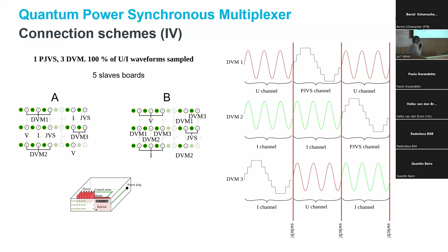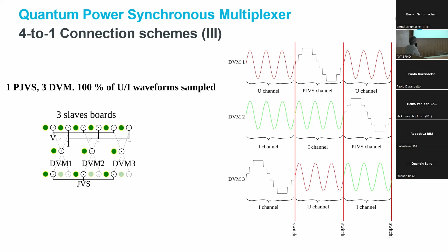And in the case you have a 4-to-1 slave board, it's more simple because now you don't need to connect externally to a slave board. You just connect the DVM in the center of the front panel, and you have voltage, current, and Josephson signal at the output. And if you have 2 DVMs, now you need to add an external connection for voltage and for current, and you need 3 slave boards. So 1 PJVS and 3 DVMs. You want to measure a 3-phase system with 3 DVMs.